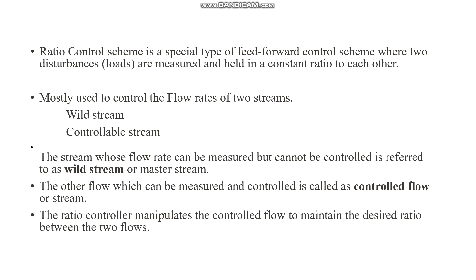What is meant by wild stream and what is meant by controllable stream? The wild stream means the stream whose flow rate can be measured but cannot be controlled. It is called the wild stream or master stream. The other stream is called the control stream or controllable flow.